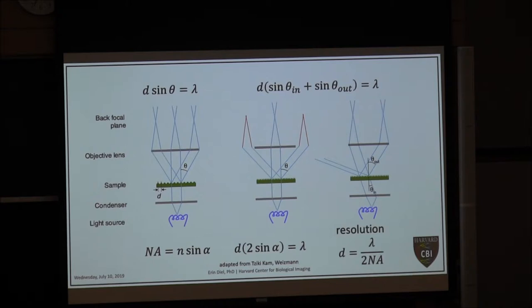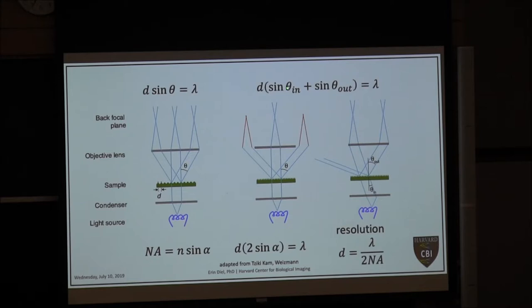When you align your microscope for Köhler illumination, it's important to have condenser and objective in the appropriate positions. The objective is usually easy because your sample needs to be in focus. But there are ways to verify whether your condenser is in the right position — there are great YouTube videos on this, and you can stop by the facility to discuss it. Also, for the factor-of-2 resolution improvement to hold, the NA of your condenser and your objective need to match — or you pick whichever NA is lower.